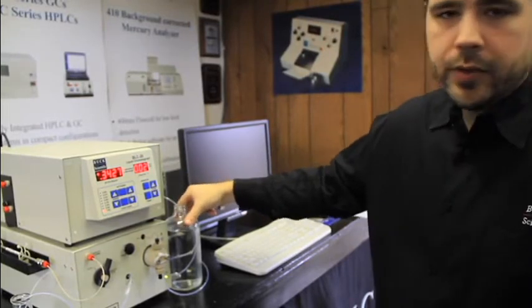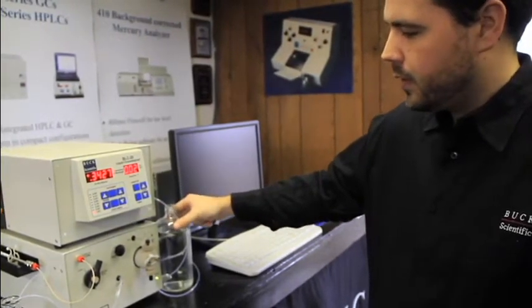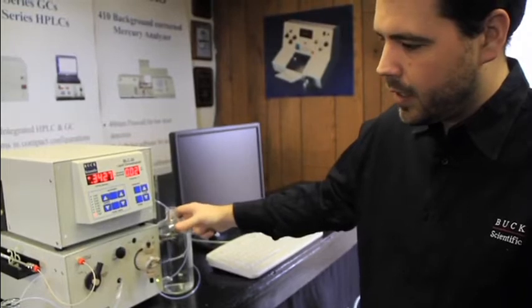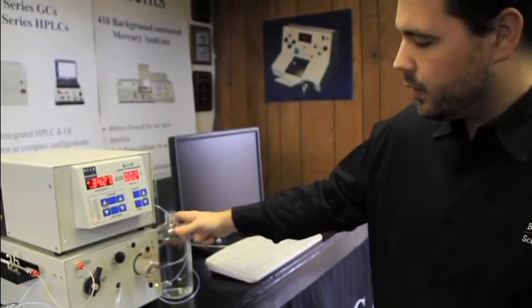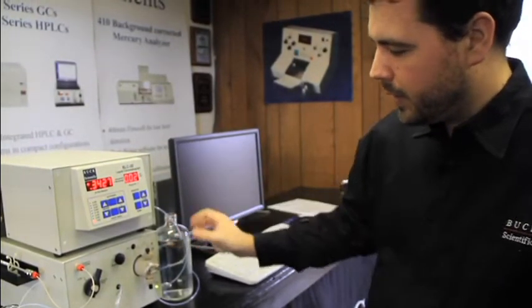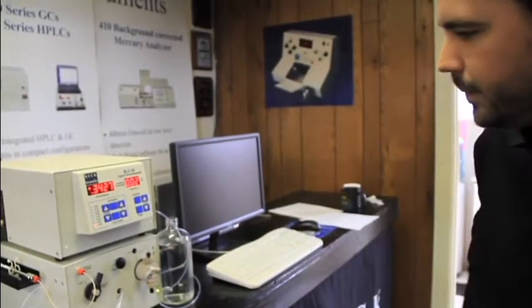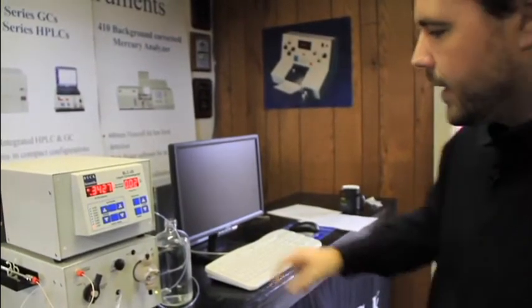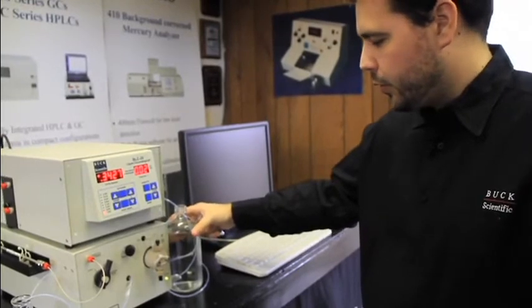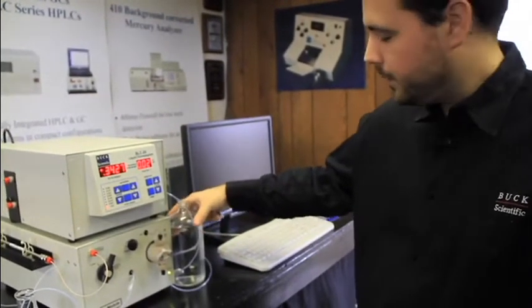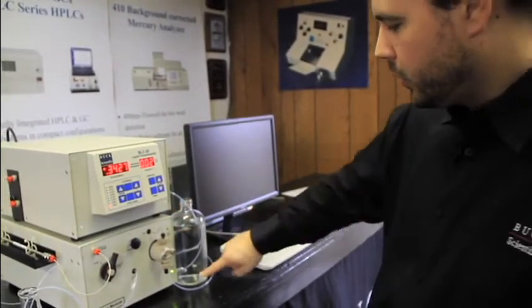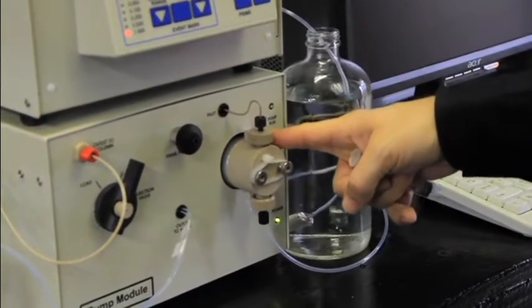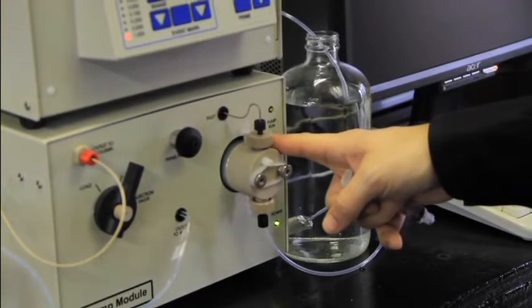It's important to use HPLC grade solvents. These ensure the lifetime of the column and the pump heads are as high as possible. The next step we're going to do is we're going to prime the pump head.